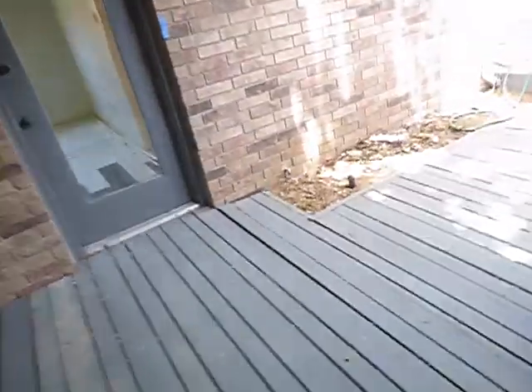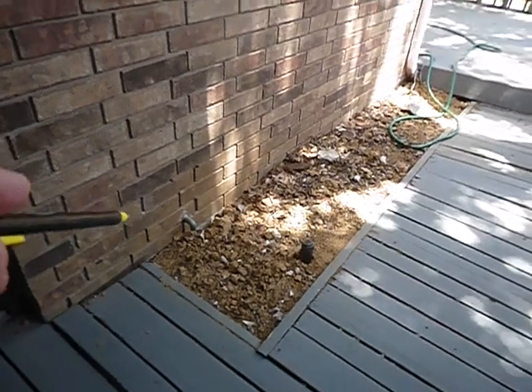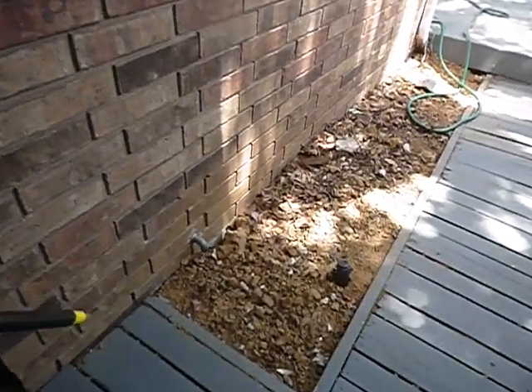Insulation is off of this patio door. This is the water heater temperature-pressure relief valve drain. They're supposed to terminate between three and six inches from the ground — that's about three inches, maybe four. That's about six inches from the ground, so that's positioned well.